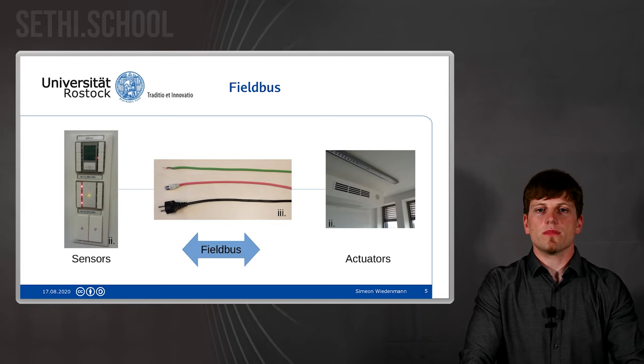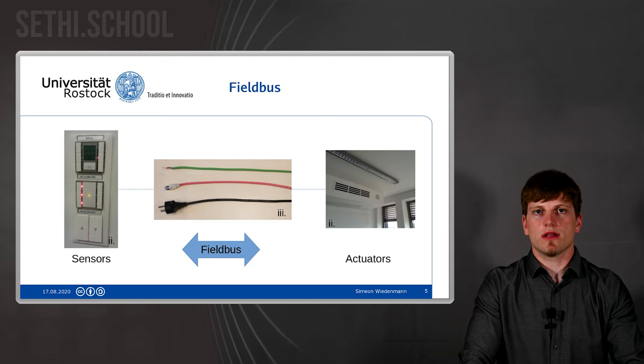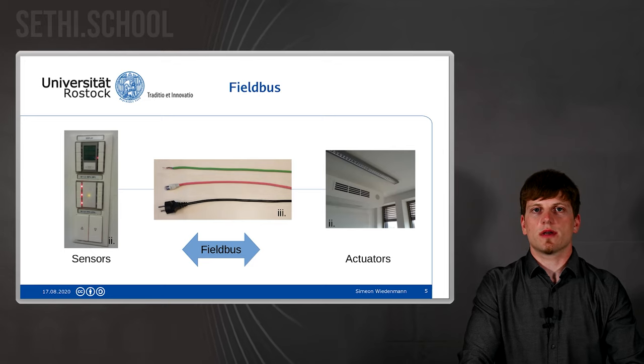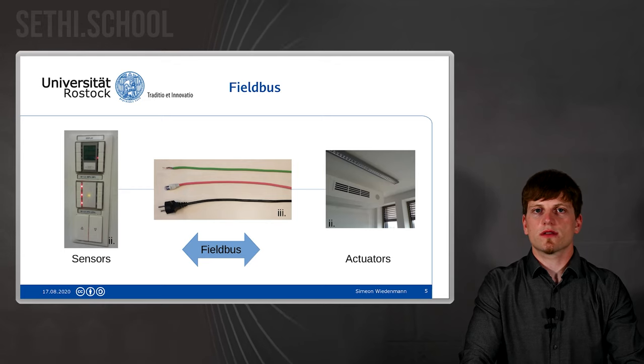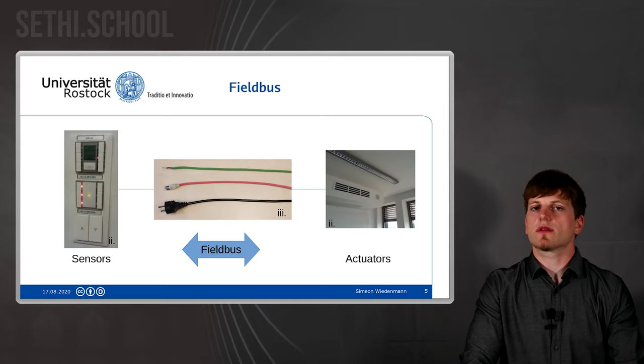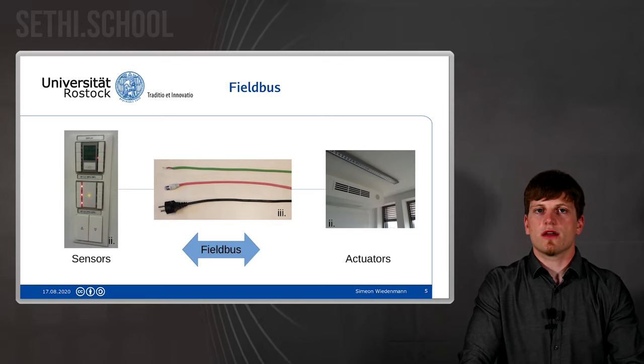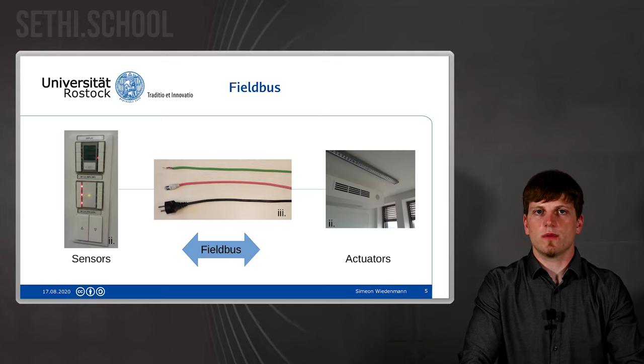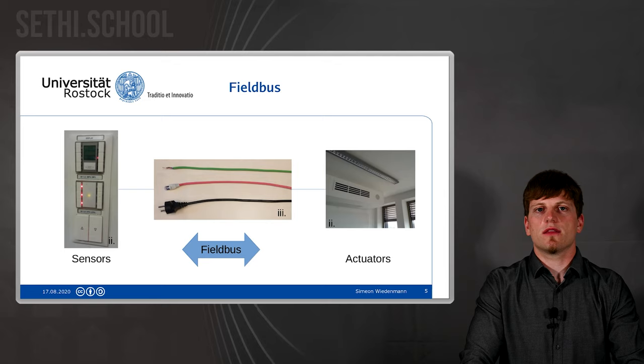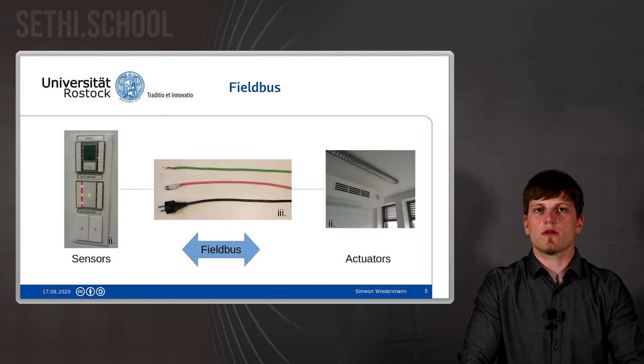We call them smart because they possess processing power, some computational power, which they use to perform communication with others. It is not the traditional one where a light switch is hardwired to a lamp and you intercept the circuit. Field bus systems used for lighting in buildings are different. The bus provides power supply to all components — since they are computational components they need power, even the switch — and then there are only telegrams sent which will alter the behavior of actuators, like a light.